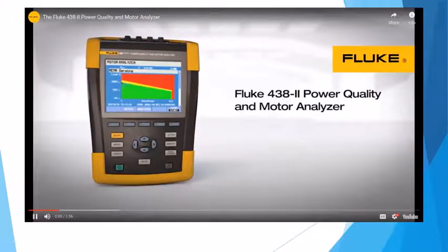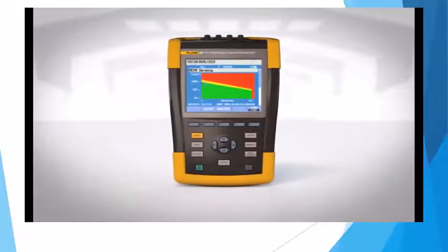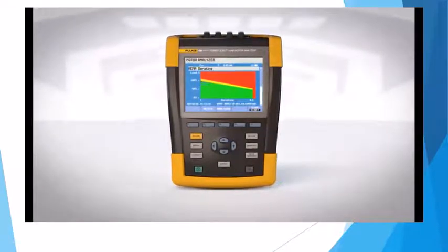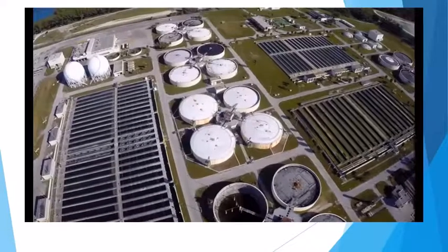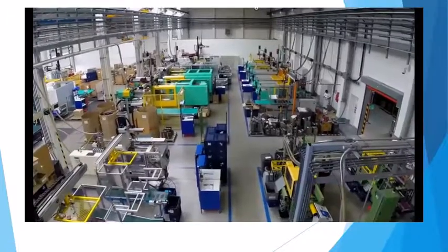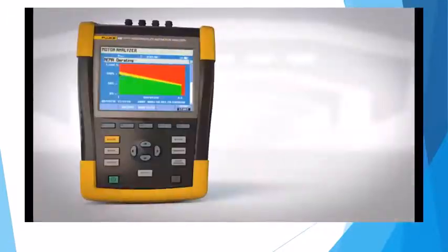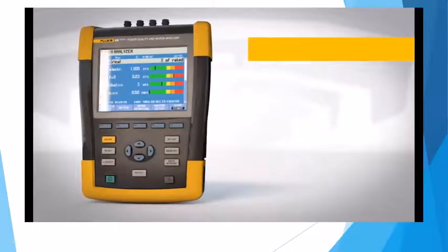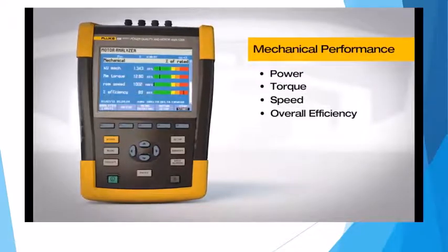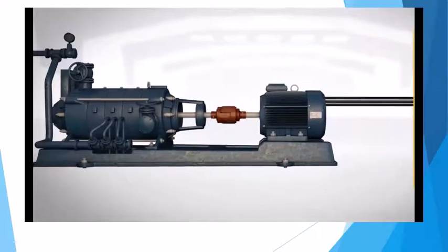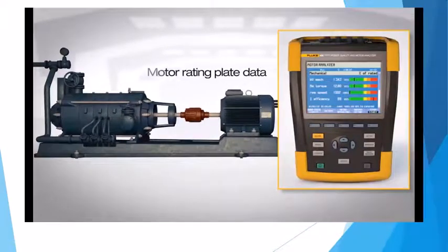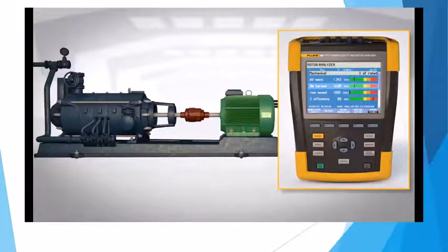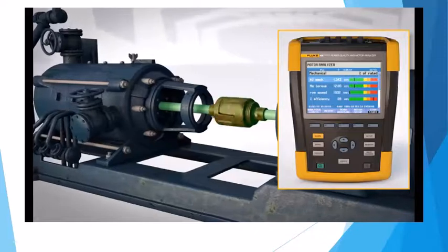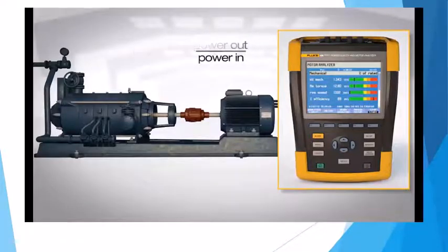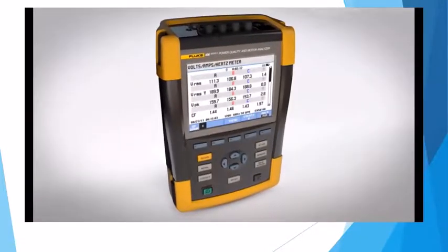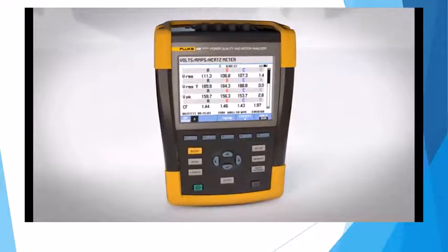Introducing the Fluke 438 Power Quality and Motor Analyzer. The Fluke 438 is a multi-purpose test tool designed to improve troubleshooting on electric motors and minimize downtime. Whether you're in a process plant or discrete manufacturing, electric motors are critical to your operation's success. The Fluke 438 lets you quickly gauge electrical performance, power quality, and mechanical performance of industrial motors. Using three-phase electrical measurements on the input and motor rating plate data, the 438 calculates torque, the most critical mechanical performance variable, speed, load on the motor shaft, and overall efficiency, without the need to install mechanical sensors. All this with a single tool, and all while the motor is running, so you don't sacrifice uptime.